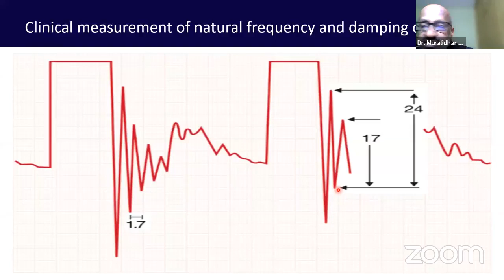And if you look at the distance between the oscillations, that depends upon the natural frequency. As I said, it should be between 10 to 20 hertz. And the damping coefficient is the ratio of the amplitude of the waveforms which are produced by the fast flush test, and it is graphically derived, and it should be between 0.4 to 0.6. And there is no unit of measurement for this value because it is a coefficient. It does not have any connotation in terms of measurements.